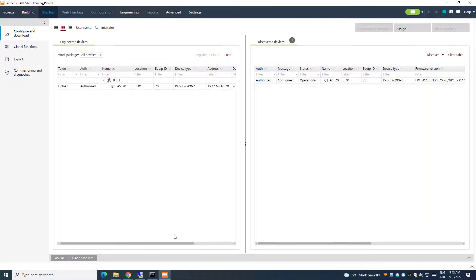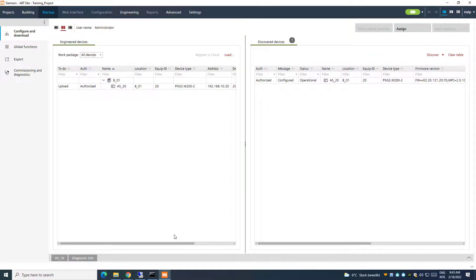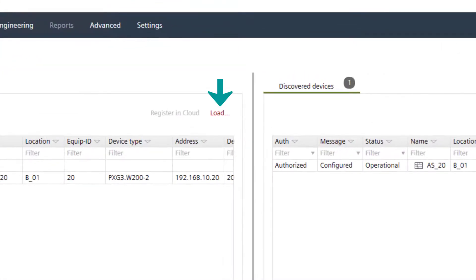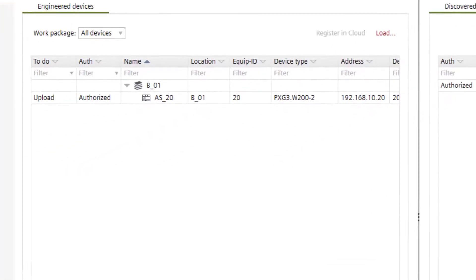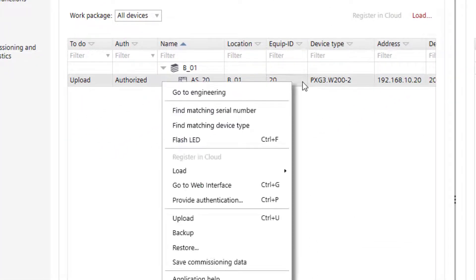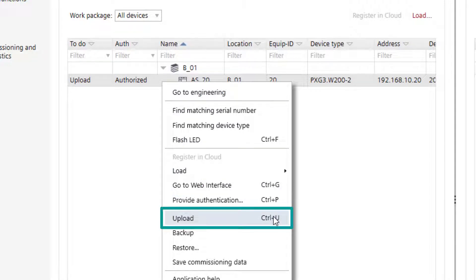In case the changes have been done only in offline mode, as we know already, it would be sufficient to perform a full load of the configuration. In case the changes have been performed only in online mode, then we can simply right-click the engineered device and upload.